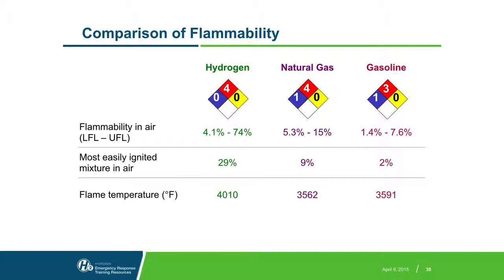The most easily ignited mixture at 29% is quite a bit higher than gasoline vapor or natural gas. But with these trade winds, do you think you're going to get to 29% very easily? Honestly, the industry understands these properties, and so the systems are designed such that between the hydrogen gas sensing and the ventilation, you're hard-pressed to get anywhere near this 29%. If you do have a hydrogen flame, and we'll see one outside and on video, the internal flame temperature is quite hot. However, there's very low radiant heat. The internal flame, like if you stuck your hand in it, you're going to get burned, but you can get your hand pretty close to it before you feel that heat, because there's no carbon. Carbon's what gives that radiant heat. Nice campfire, nice and hot, burning the wood. No carbon means no or very little radiant heat.